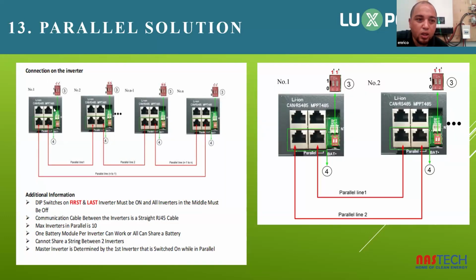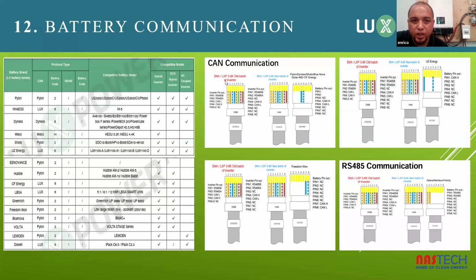For paralleling solutions, the first and the last dip switches of the inverter need to be up. On my right-hand side here are 2 SNA 5 kilowatt inverters. So you will daisy chain the parallel comms cable: the first slot to the last slot of the second inverter, and then the last slot of the first inverter to the first slot of the second inverter. If you have two inverters, both dip switches need to be up. If you have more than two inverters, 3 or 4, the tip is that the first and the last dip switches of the first and the last inverter are up, and those in between are down. Here where the battery comes in, you'll see the red dip switches are the older version, and the blue dip switches are the newer version.